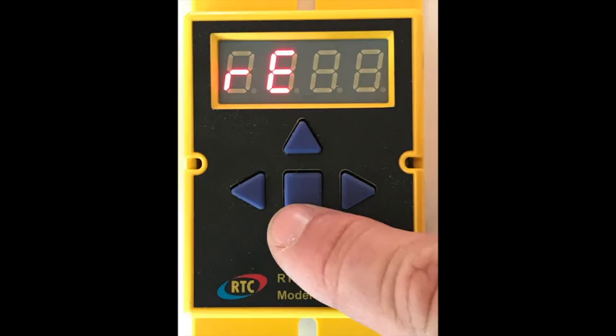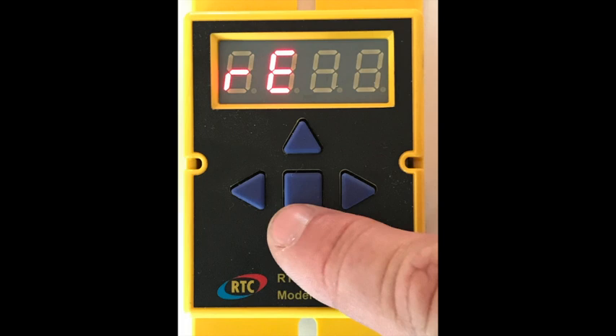The next menu is RE. This stands for remote. Your options here are to enable or disable, which will turn on or off the 0 to 10 volt DC input terminal. If enabled, the motor speed will be controlled by this signal, not the speed set point. This allows the speed controller to receive a 0 to 10 volt DC input signal, which will in turn control the motor speed. So if the controller received 5 volts DC on the input terminal, the motor would run at 50% of max.